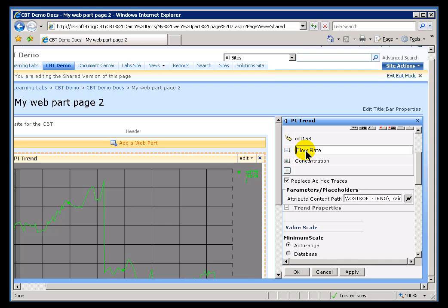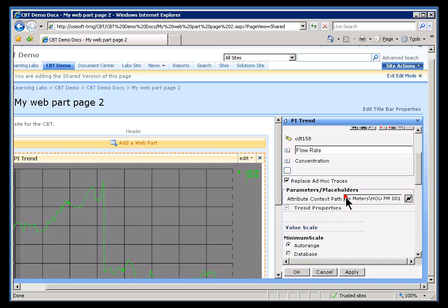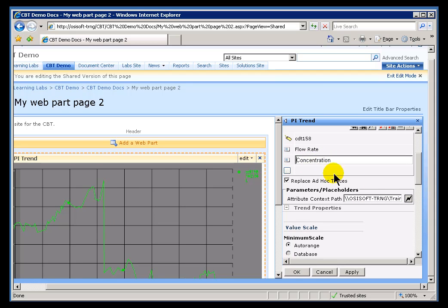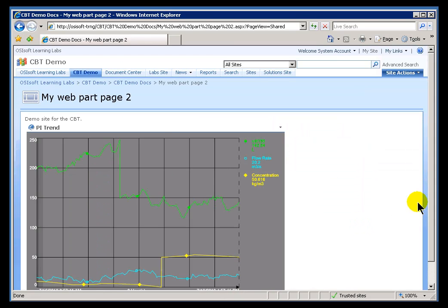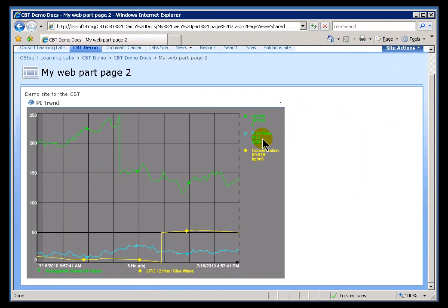When we map this Flow Rate with this Context Path — and if we look all the way over to the end — you can see this is that section on Flow Meters. If we look at Concentration, that's the name of the Attribute, but if we go all the way over in the Context, you can see this is coming from that Tank. So it's the two of these together — the Name of the Attribute and the Context of that Attribute — that allow us to figure out which PI Tag is associated with that as a Data Reference. And that's of course what we Trend.